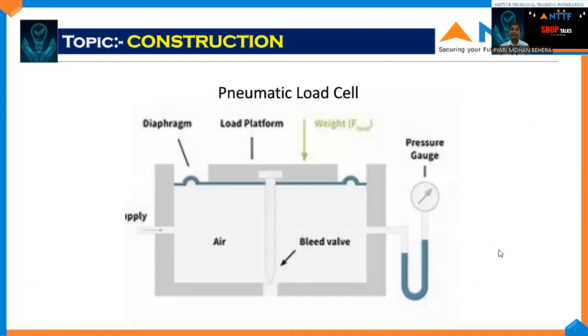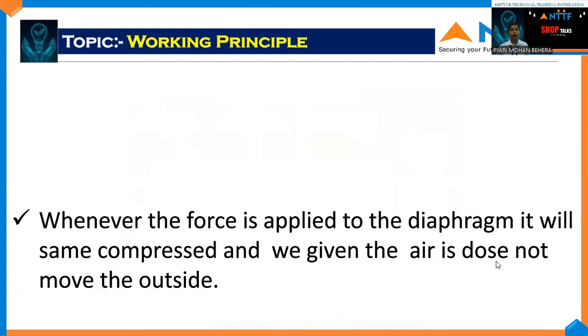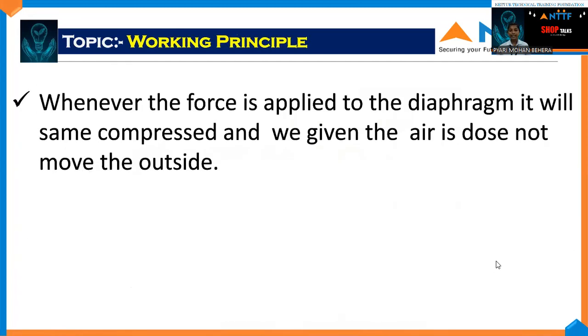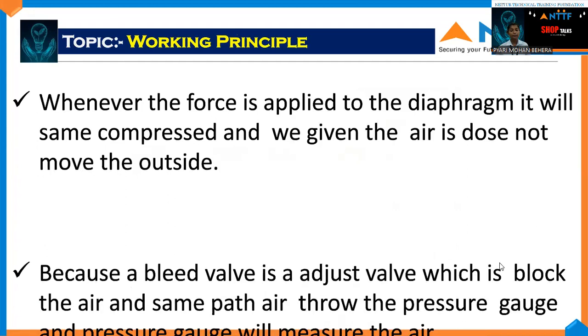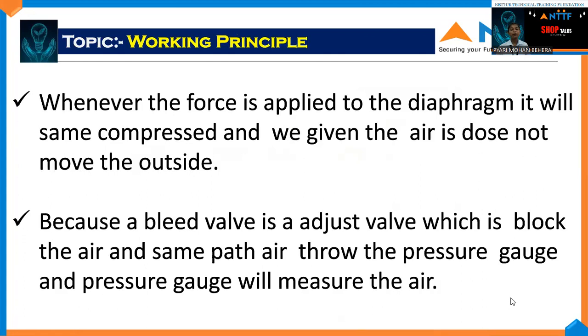Then construction diagram of pneumatic load cell. Pneumatic load cell consists of load platform, diaphragm, air supply, bleed valve, and pressure gauge. Then working principle of pneumatic load cell. Whenever force is applied to the diaphragm, it will compress, and the air does not move outside because a bleed valve is there. Bleed valve is an adjustable valve which blocks the air and lets it pass safely through the pressure gauge, and the pressure gauge will measure the air.